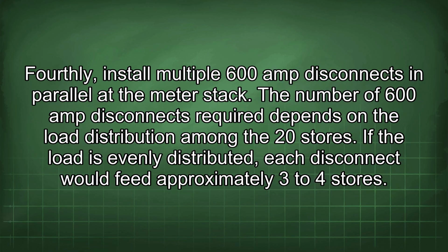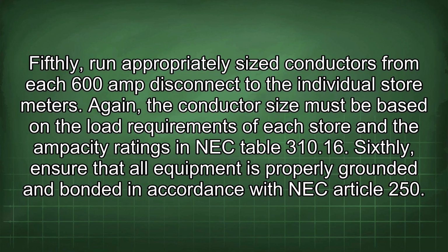Fourthly, install multiple 600 amp disconnects in parallel at the meter stack. The number of 600 amp disconnects required depends on the load distribution among the 20 stores. If the load is evenly distributed, each disconnect would feed approximately 3 to 4 stores. Fifthly, run appropriately sized conductors from each 600 amp disconnect to the individual store meters. Again, the conductor size must be based on the load requirements of each store and the ampacity ratings in NEC Table 310.16. Sixthly, ensure that all equipment is properly grounded and bonded in accordance with NEC Article 250.